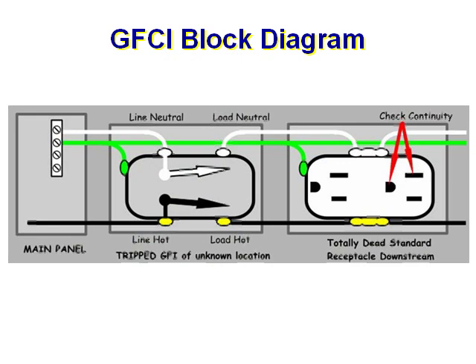Water is a conductor. Ground fault circuit interrupters, GFCI, or ground fault interrupters, GFI, are used in bathrooms, garages, exterior wiring, and in wet areas in general where there may be other conducting paths to ground. The GFCI detects the difference in outgoing and returning current. If they are not equal, then there is a leakage current somewhere that could be going to ground through the operator of the tool. The GFCI connects between the circuit breaker and a power plug.